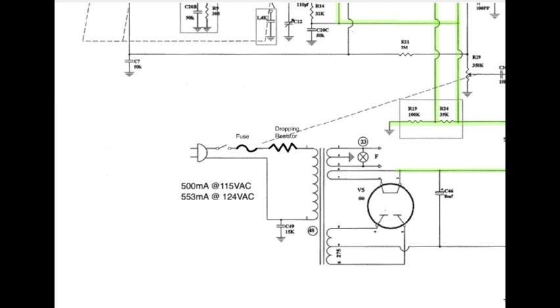Once that's done, the amount of current flowing through the transformer is reduced, down to our nominal 500 milliamps. But while it's charging and heating things up, it's quite a bit more than 500 milliamps. That's called inrush current, and it's hard on the transformer - it's kind of hard on the circuits. So if you could limit the amount of current going in, slow it down so it more slowly heats up the tubes and charges the capacitors, that might be a good thing to do.